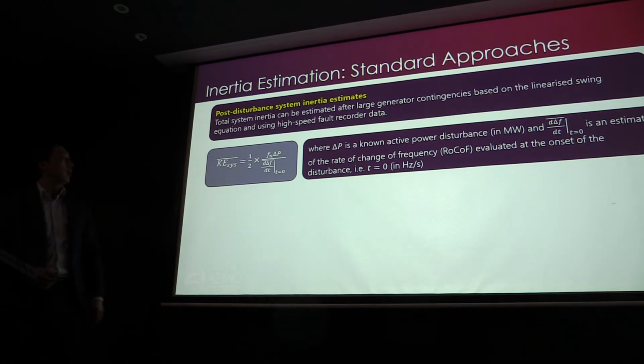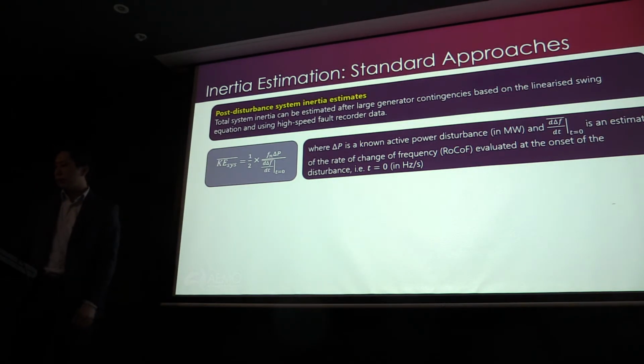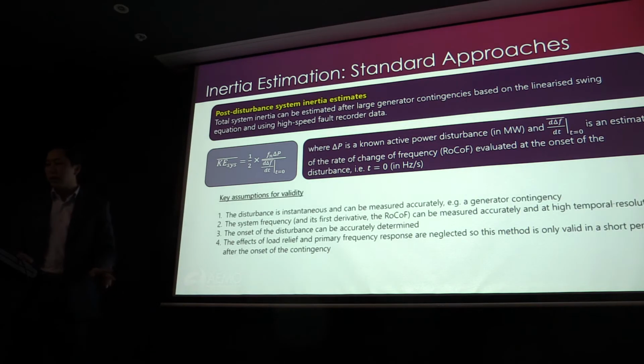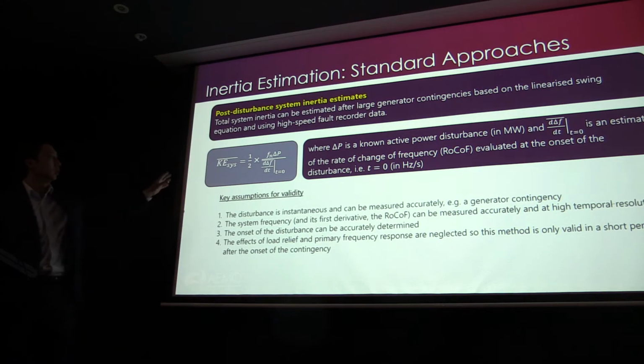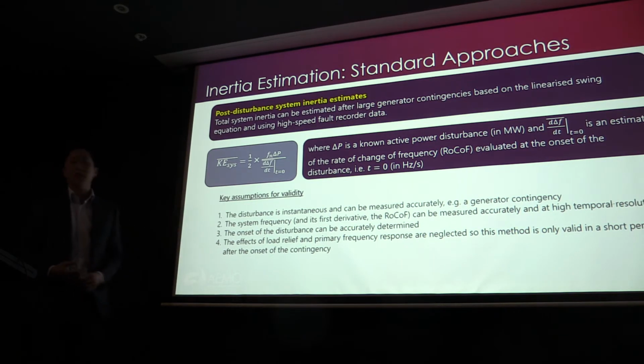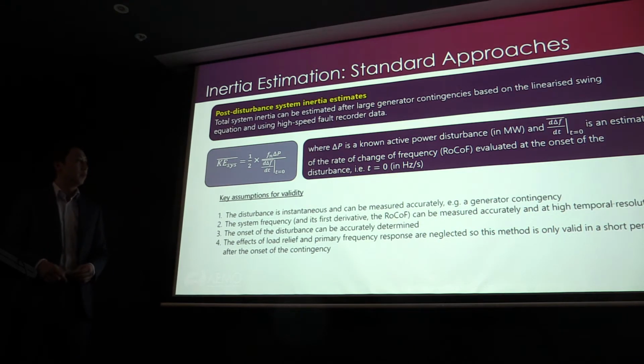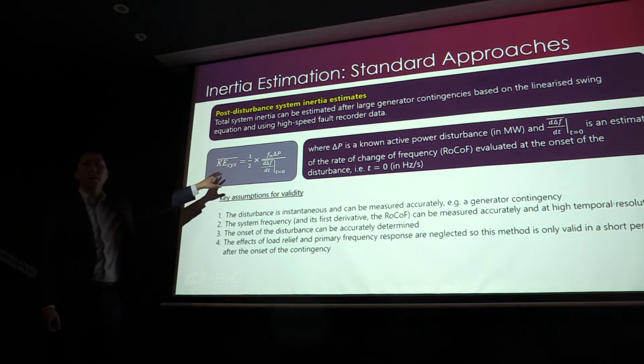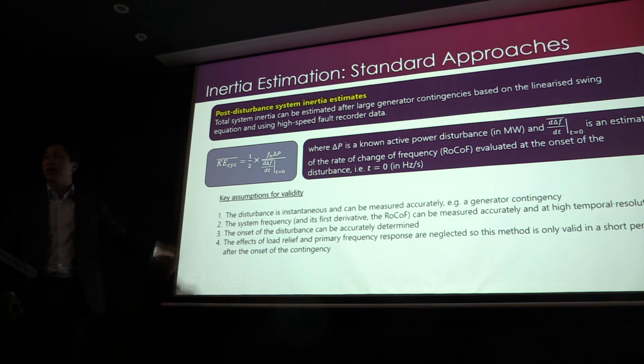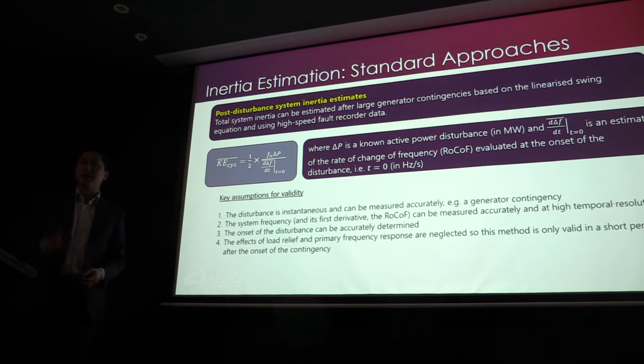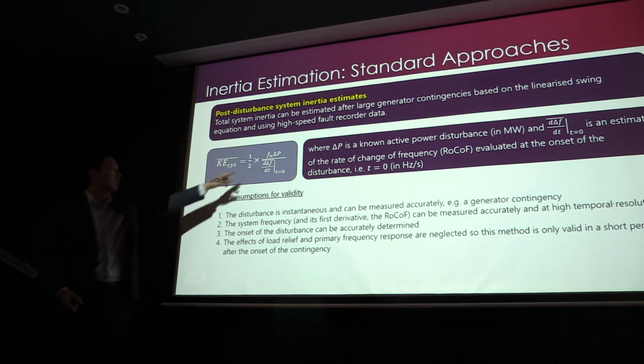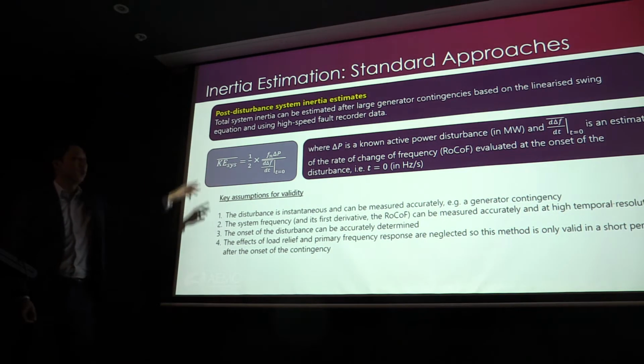And then you calculate the rate of change of frequency based on the frequency trace itself. There are some caveats here, and this is only valid under certain conditions using a linearized swing equation. So first of all, the disturbance has to be instantaneous. If you start trying to feed in a ramp, then this no longer applies, because you'll have primary frequency response starting to act and so forth, and these sort of simplified formulations no longer are valid.